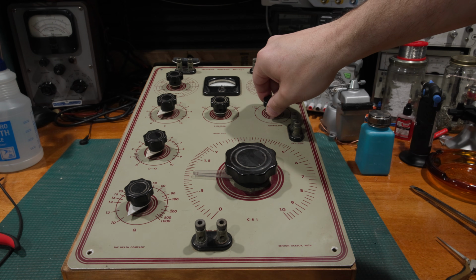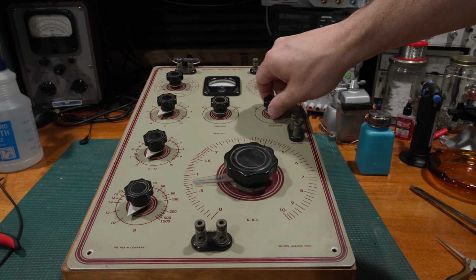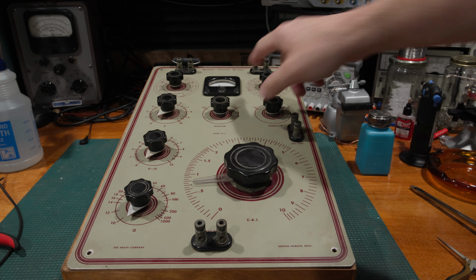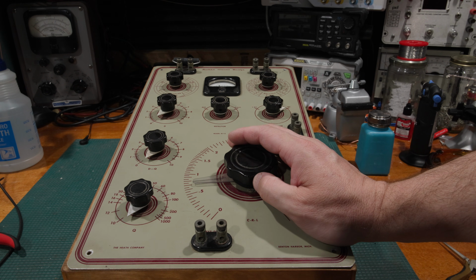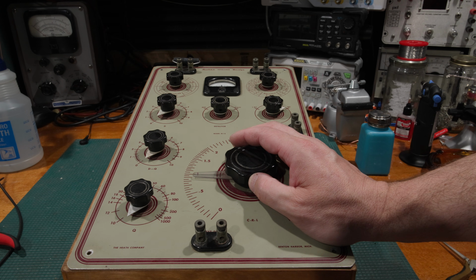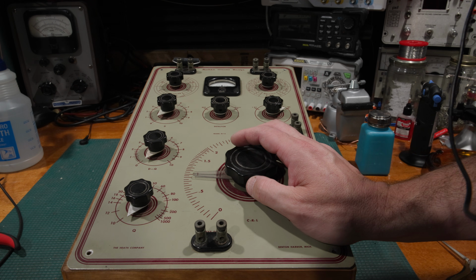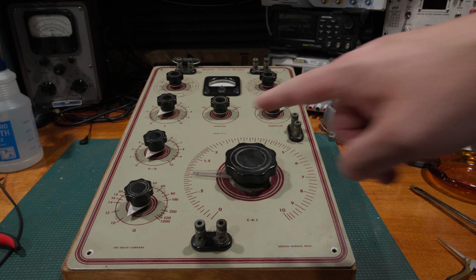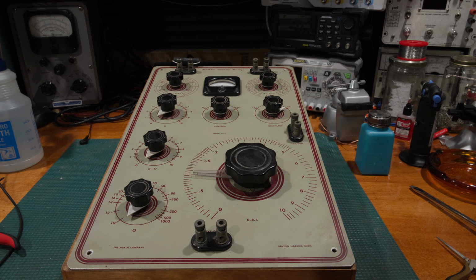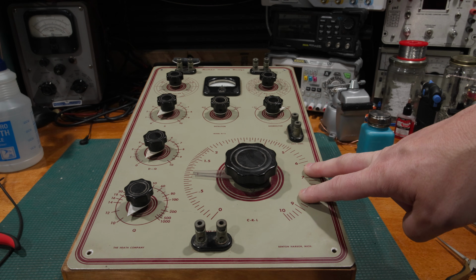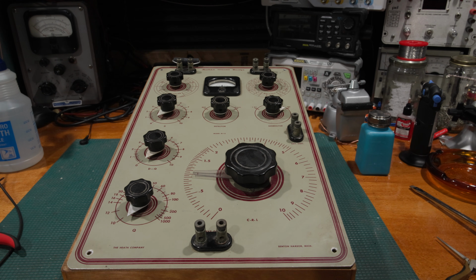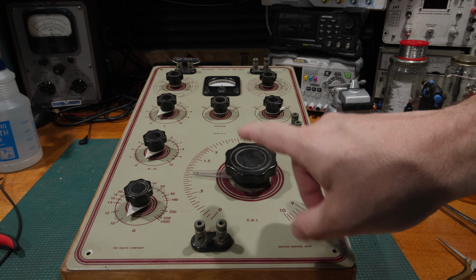So what we're going to do, kick this over to DC. We'll back this off a little bit. And we have deflection on the meter, which is good. Zero this. Call it right about there. And we can see we're off by about one tick on the main control over here. So what we're going to do is adjust the calibration. This is to calibrate this unit. It is a very gross calibration. I actually loosened the control and move it till it lines up without disturbing the meter.